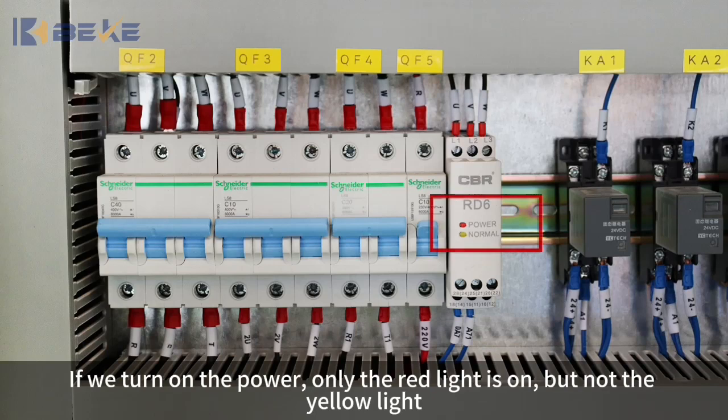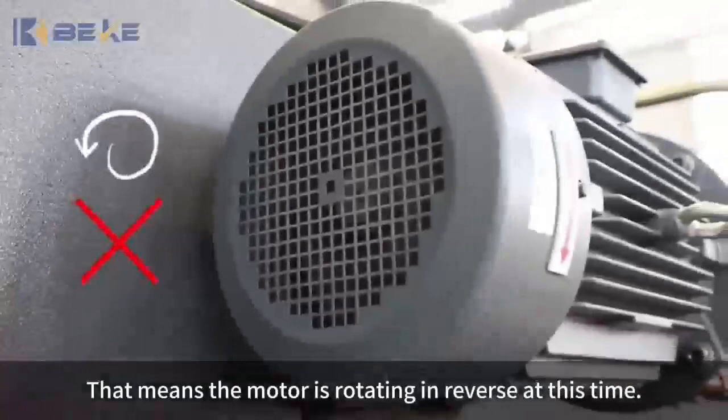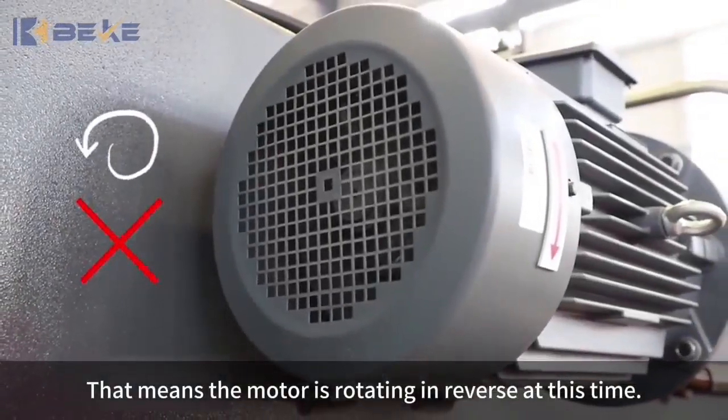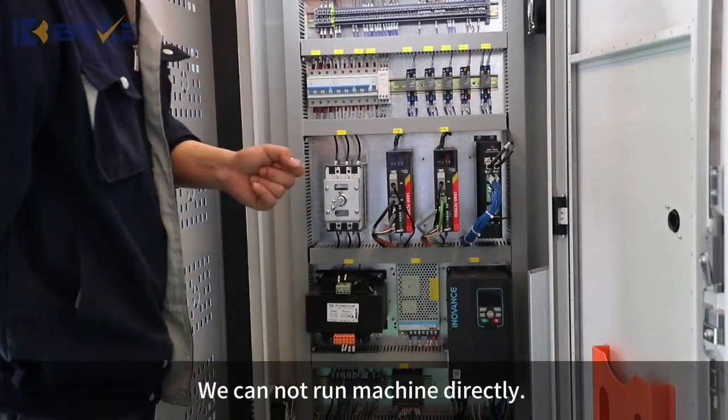If we turn on the power, only the red light is on but not the yellow light. That means the motor is rotating in reverse at this time. We cannot run machine directly.